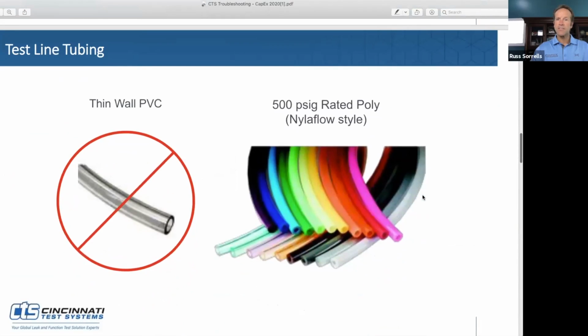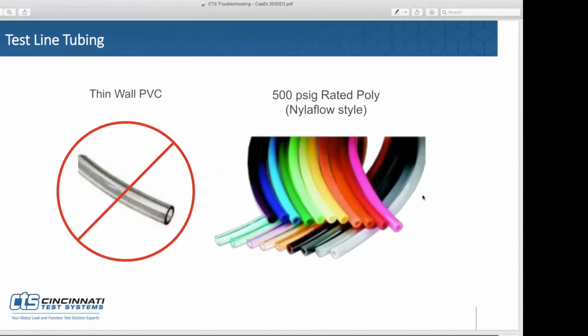Absolutely. Test line tubing. Yeah, and then test line tubing. You heard me say a positive lock on your tubing. Well, if you have thin wall PVC tubing, you're not going to get a great positive lock. And then two, thin wall PVC or even rubber is going to expand under pressure. So you're going to see that same movement we were talking about earlier, where volumetric change is equated to an actual leak rate and false accepts or rejects based on its expansion and contraction. So our suggestion: 500 psi nylon style tubing or higher. We use a lot of 1,000 psi rated tubing.